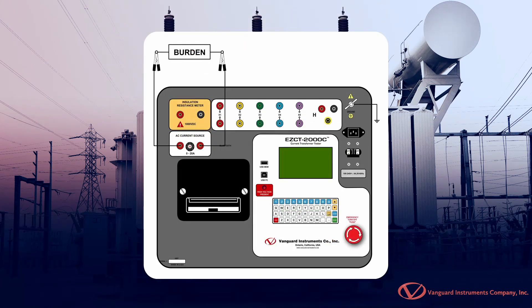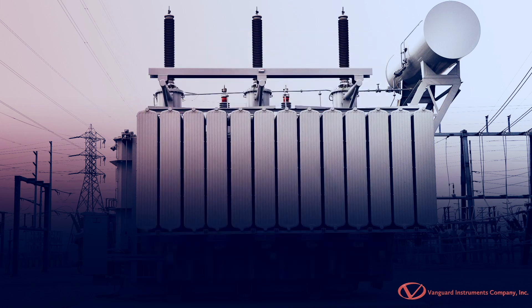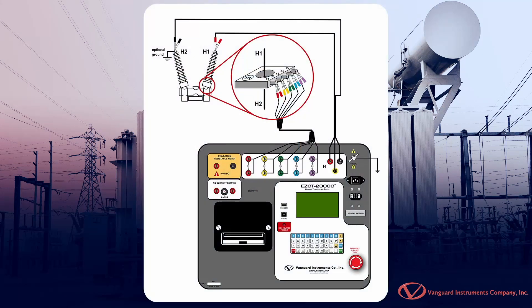Lastly, it provides a programmable current source that can be used to verify CT loads. To perform an excitation test, we'll make connections per this diagram.